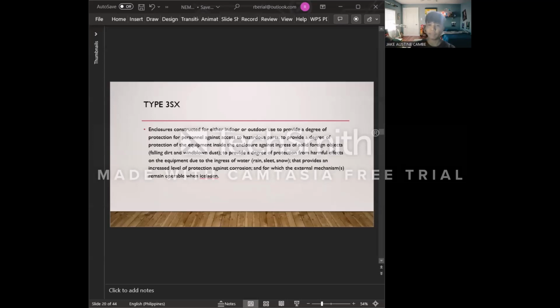Next is yung type 3SX. Type 3SX enclosures are constructed for either indoor or outdoor use to provide a degree of protection for personnel against access to hazardous parts. Next is to provide a degree of protection of the equipment inside the enclosure against ingress of solid foreign objects, for example, yung falling dirt and wind-blown dust.